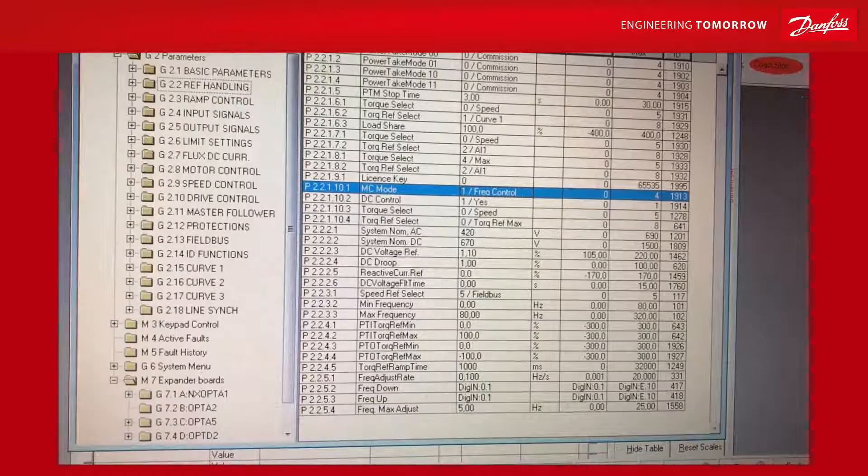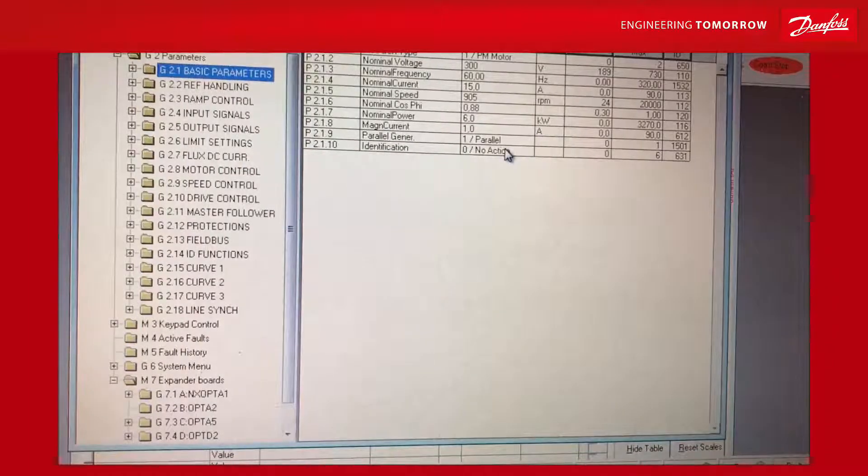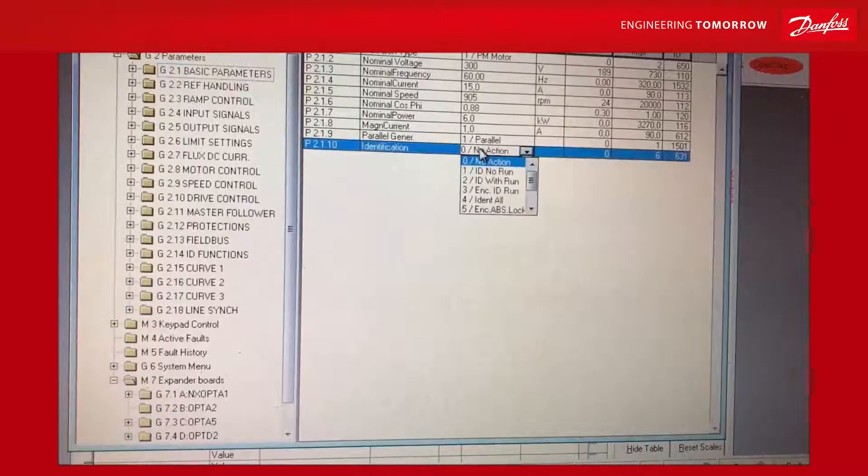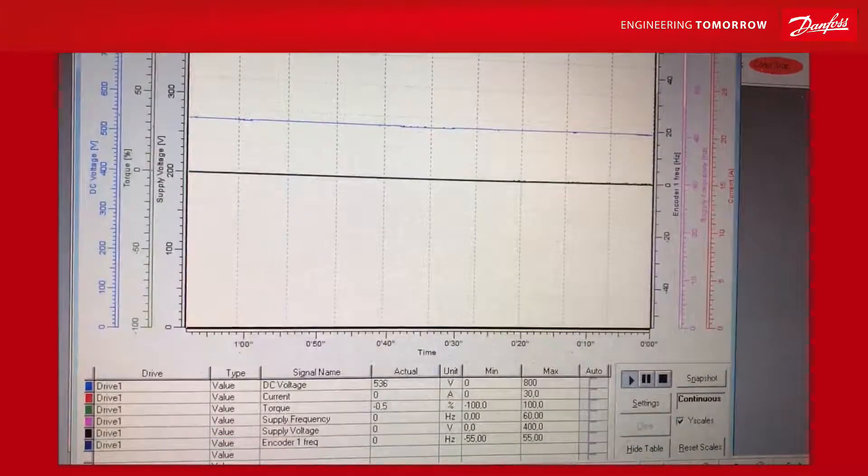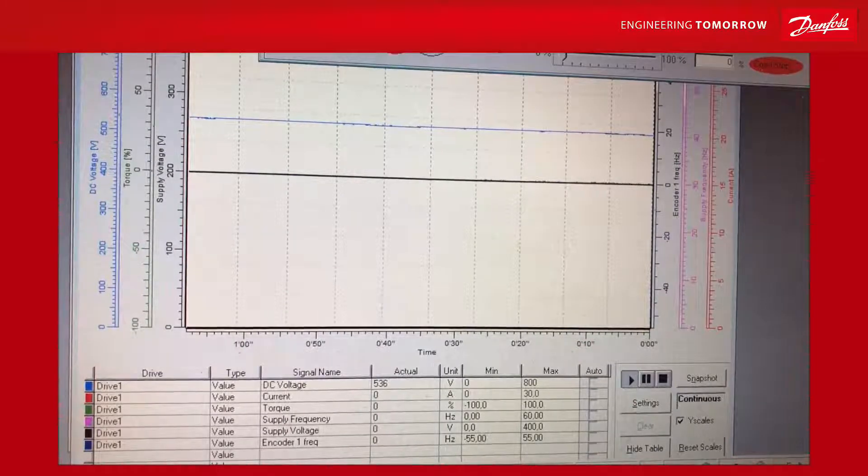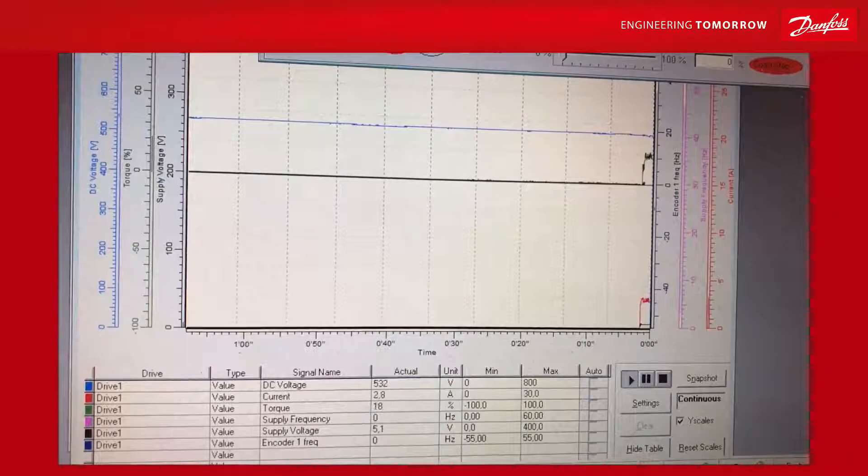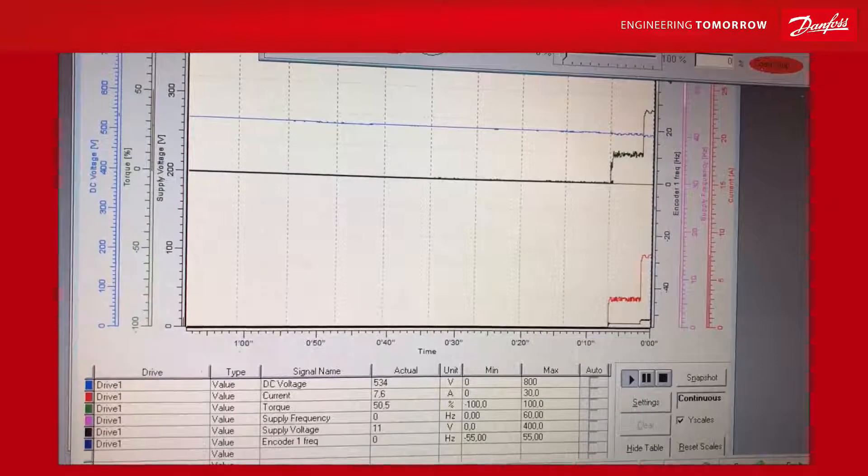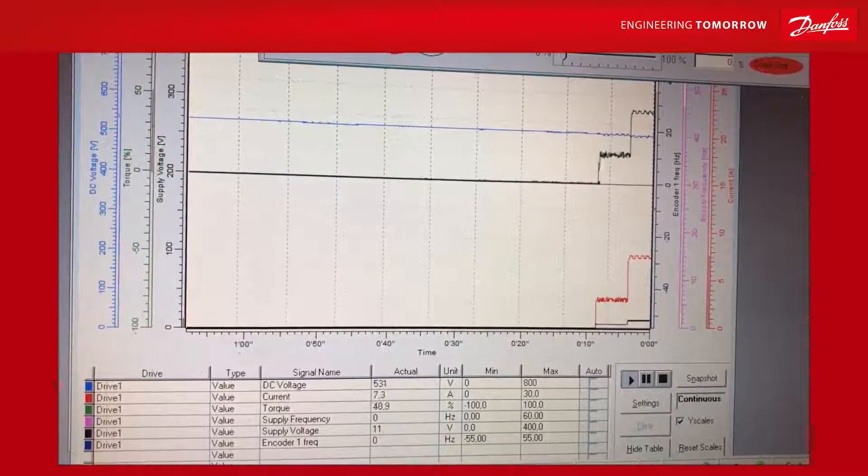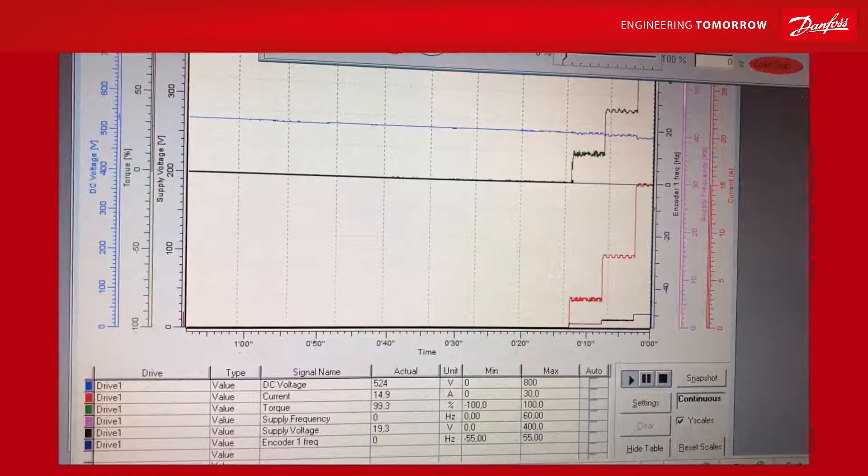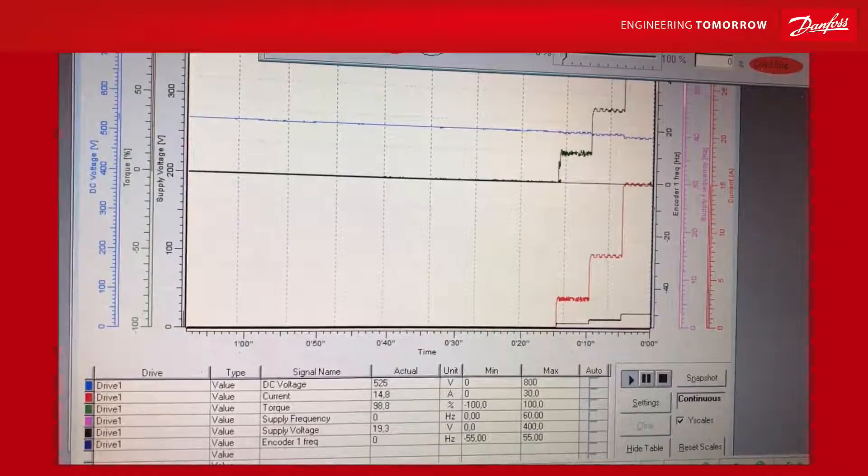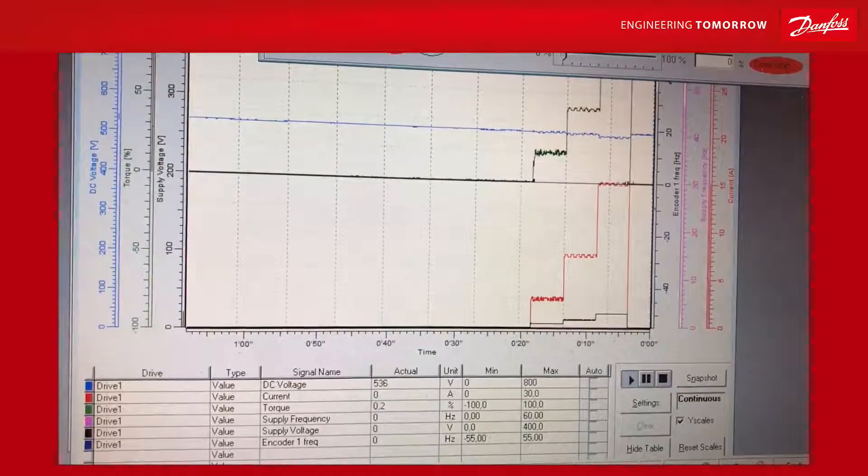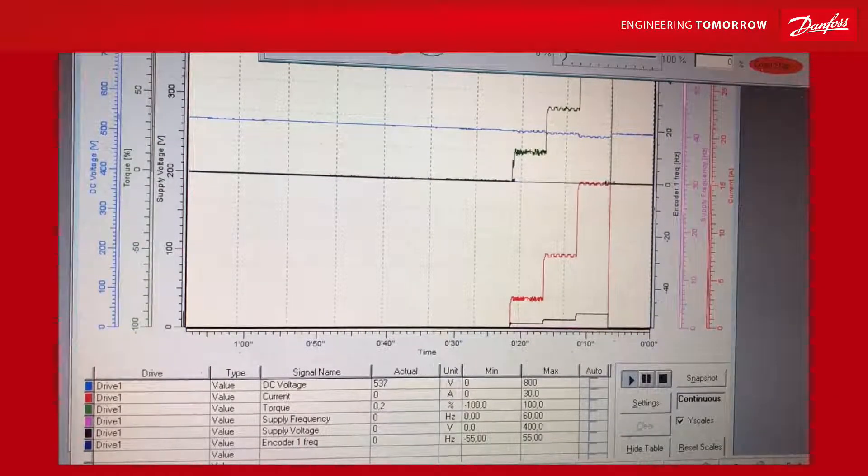Then we do the identification at zero speed. We go to basic parameters and select identification ID with no run. We take a look at the current to see what's happening with the motor. We start it manually and it will make some noise as it puts current to the motor. What's actually happening is measuring the stator impedance, the resistance in the copper.